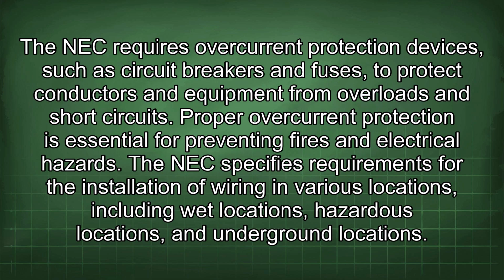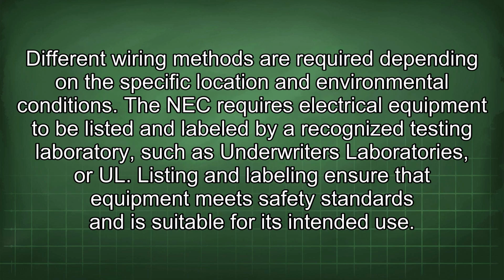The NEC requires overcurrent protection devices, such as circuit breakers and fuses, to protect conductors and equipment from overloads and short circuits. Proper overcurrent protection is essential for preventing fires and electrical hazards. The NEC specifies requirements for the installation of wiring in various locations, including wet locations, hazardous locations, and underground locations. Different wiring methods are required depending on the specific location and environmental conditions. The NEC requires electrical equipment to be listed and labeled by a recognized testing laboratory, such as Underwriters Laboratories or others. Listing and labeling ensure that equipment meets safety standards and is suitable for its intended use.